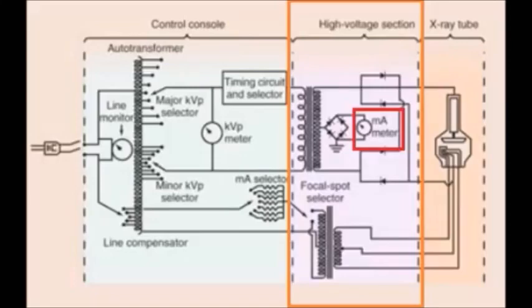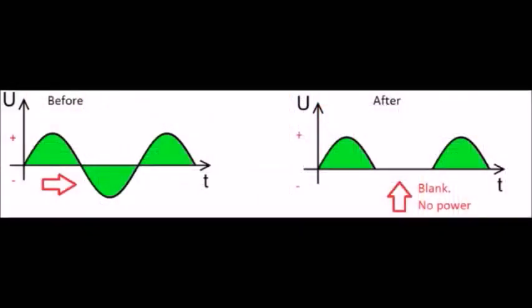It is safely connected to an area that has no voltage from the step-up transformer. Power then goes to the rectifiers, which convert AC (alternating current) to DC (direct current) to maintain electrons flowing in one direction from cathode to anode. Rectifiers are semiconductor solid-state PN junction diodes. Half-wave and self-rectified systems work by not conducting during the negative portion of AC current — this method is very inefficient because half of the power is wasted.